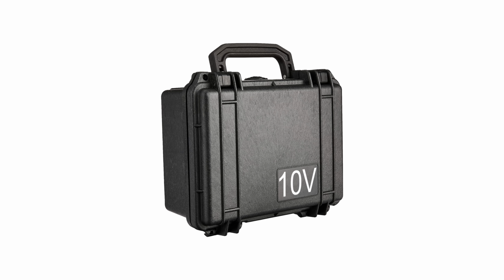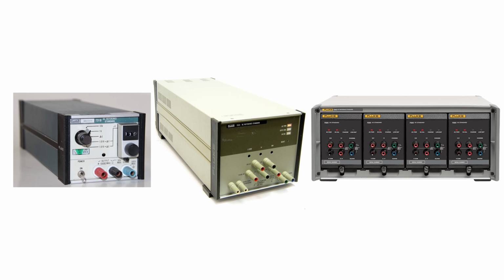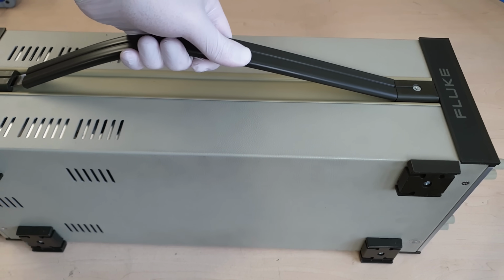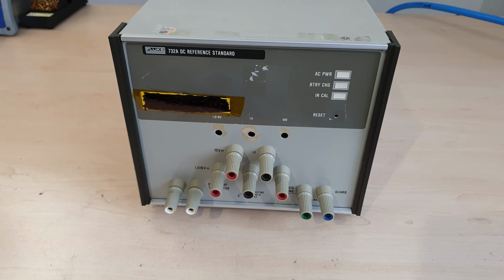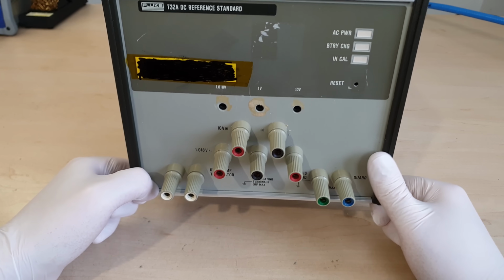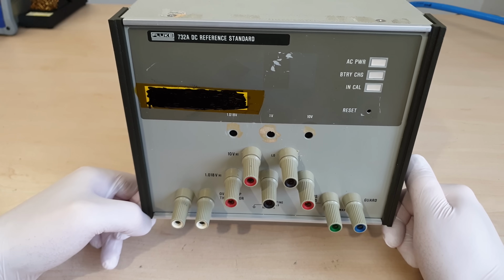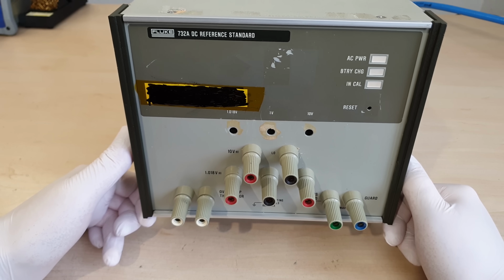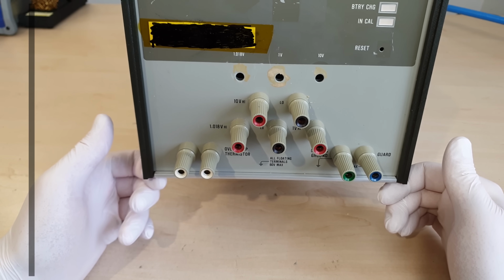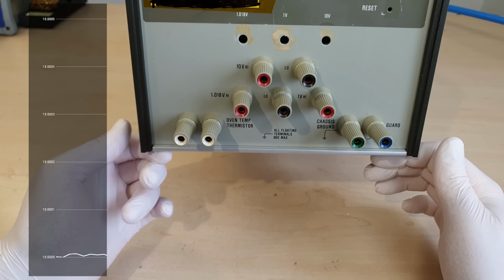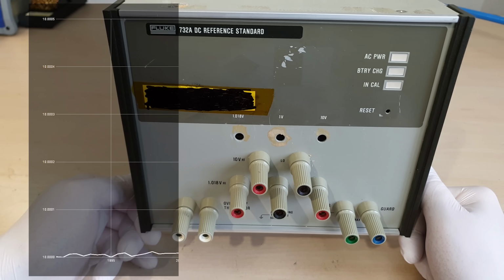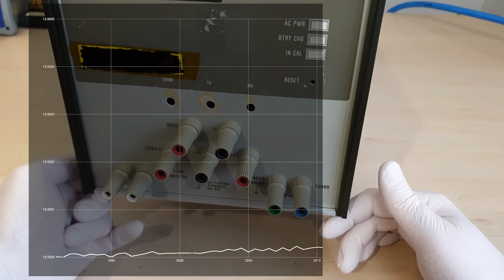There is of course the easy way of just buying one. Fluke themselves have a long history of making extremely good battery-powered voltage standards. This one, the Model 732A, is one of their earliest. It's so old, in fact, that it has a dedicated 1.018 volt output for compatibility with Weston cell systems. It is, however, Zener diode based and therefore much more robust and less drifty. The drift of this unit has been recorded for the last 30 years, and it came out to less than 0.1 ppm per year. An absolutely impressive track record, exceeding even the specifications of its successor by far.